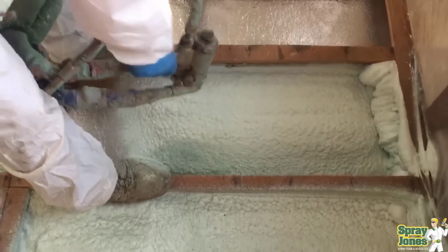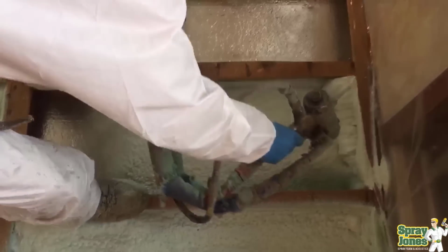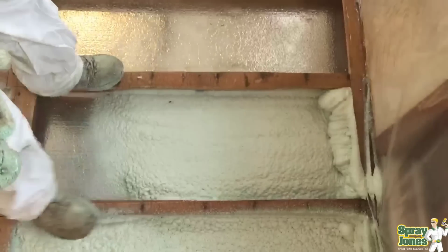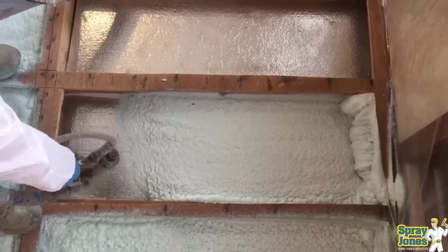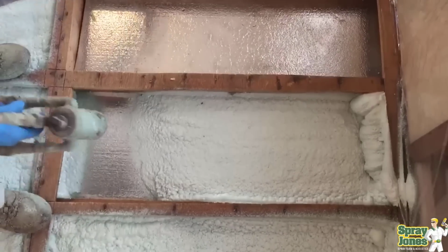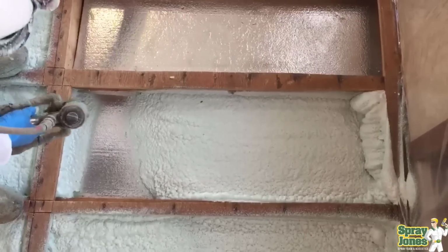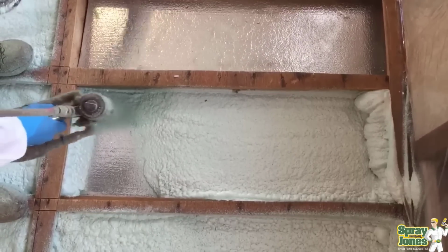Then once we had it back into where we needed, we just continued to build it up excessively thick, and then we put a spray applied liquid coating over top of it just to help it out, give it an extra little oomph of vapor control. And to this day they haven't had any more issues, no more freezing pipes. The problem is 100% gone.